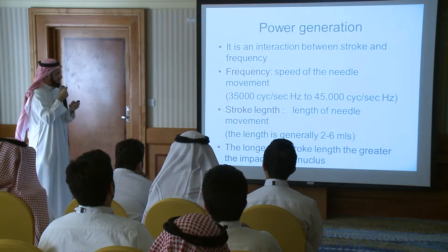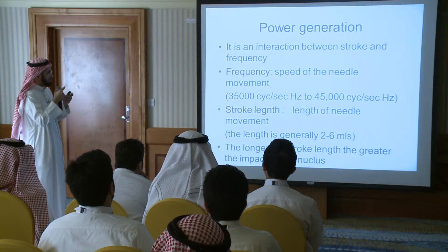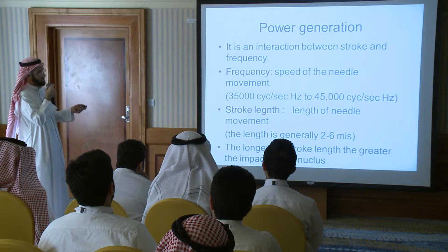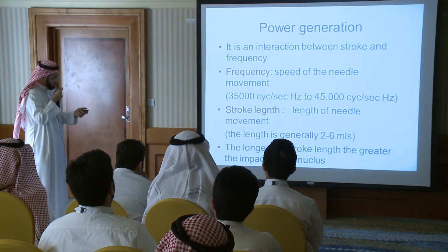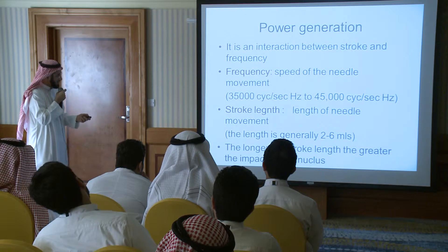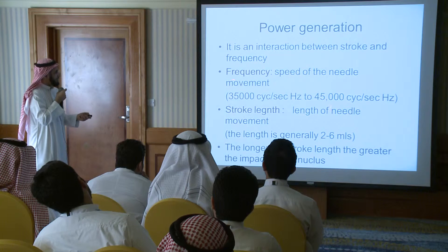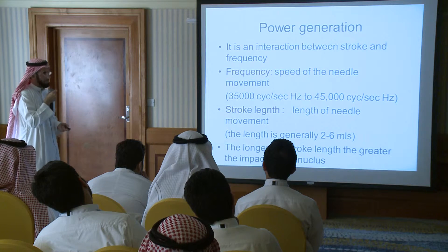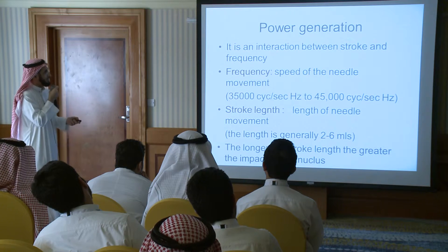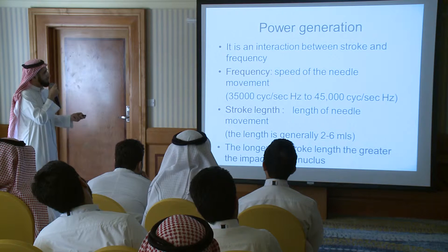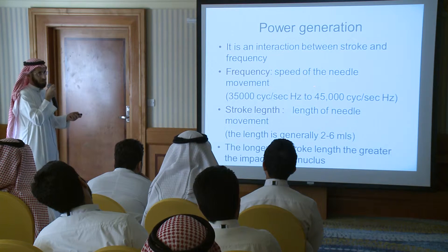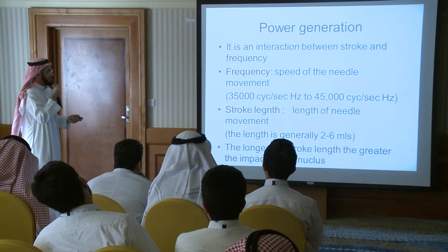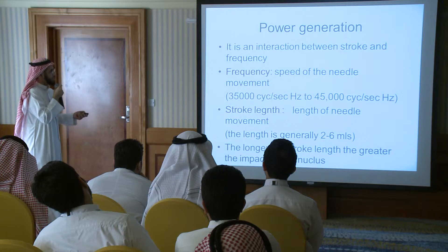Usually the range is from 35,000 cycles per second to 45,000 cycles per second. This is most of the machines they have fixed — so this is fixed, you cannot change it. So what you can change...